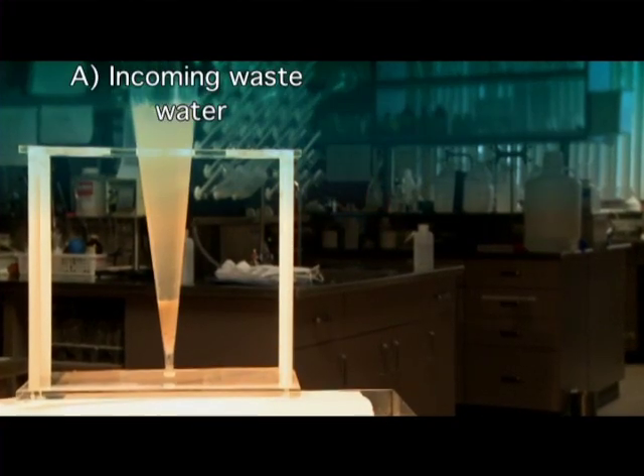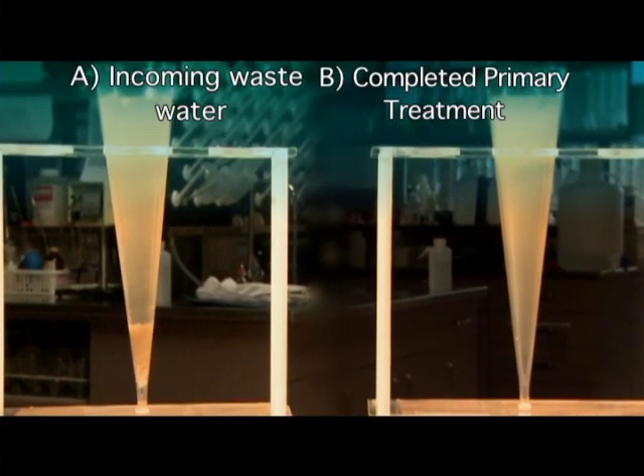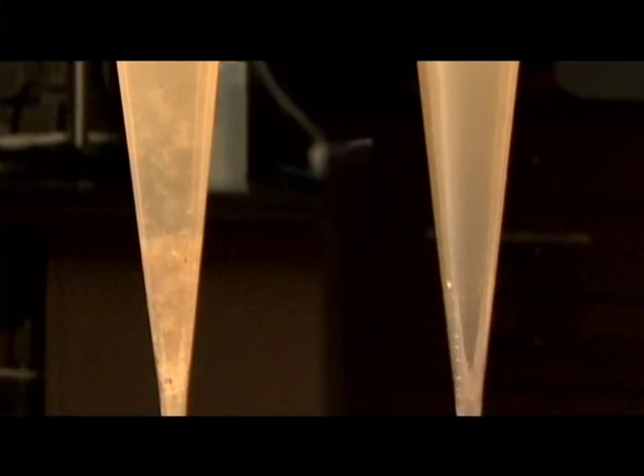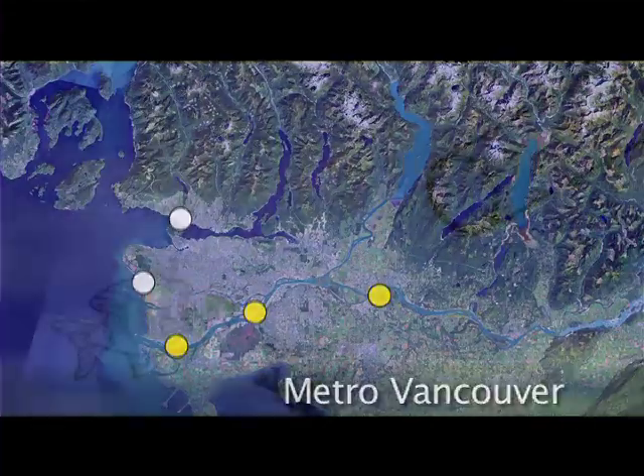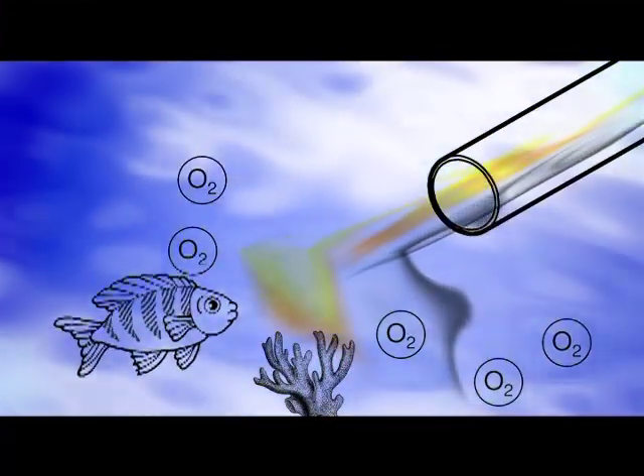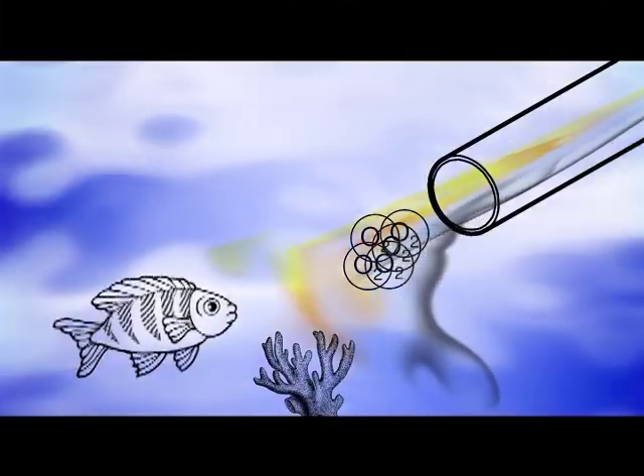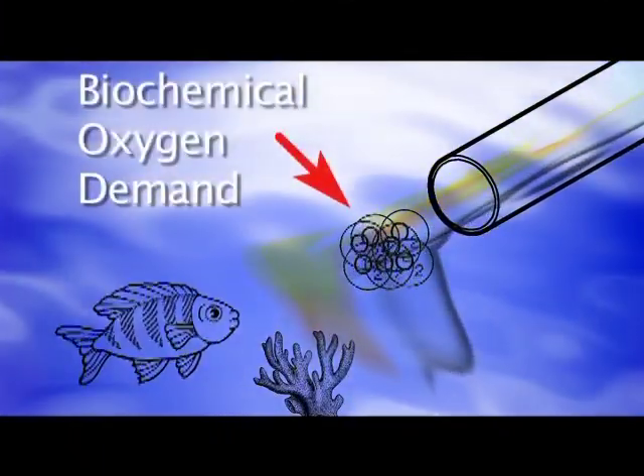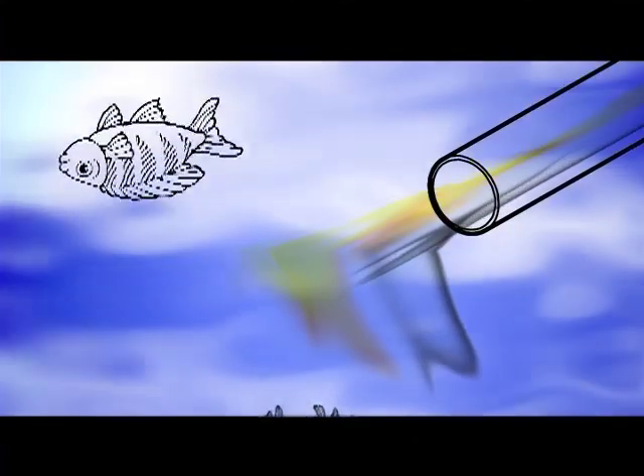Here is a sample of the incoming wastewater, and on the right is a sample following completion of primary treatment — 50% of the suspended solids have been removed. Three of our five regional treatment plants treat the wastewater even more to further protect the receiving environment. If placed into oceans or rivers untreated, it will use the same dissolved oxygen that supports aquatic and marine life. The suspended solids use up oxygen as they break down — this is called biochemical oxygen demand. If too much oxygen is used up, the water becomes uninhabitable. Here at Lulu, the wastewater goes through all these funny shaped buildings and pools, and the result is that 95% of the suspended solids are removed.